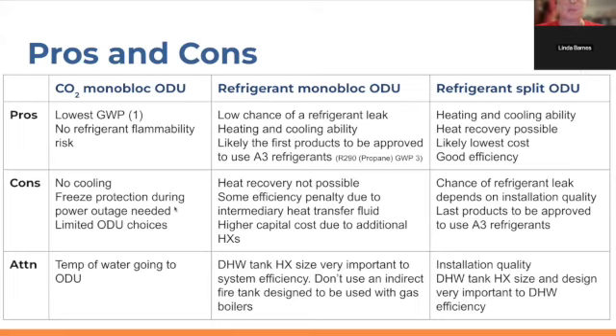Typically, with refrigerant monoblock outdoor units, heat recovery is not possible. In fact, simultaneous heating and cooling is not even possible. The only way to do simultaneous heating and cooling with a refrigerant monoblock outdoor unit is to have buffer tanks. On the end use side, it's perceived that you're getting air conditioning and space heating while you get to enjoy hot water for showers. It seems like it's happening simultaneously, but no, the outdoor unit is actually switching between recharging the domestic hot water tank in heat mode and then switching over to cooling mode in order to recharge the chilled water buffer tank on the space cooling side. That's how it's able to give you the perception that it's doing both at the same time. But physically, the outdoor unit cannot do heat recovery and cannot do simultaneous heating and cooling.